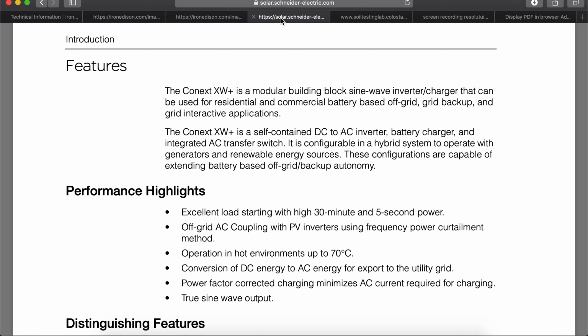The Conext XW Plus is a modular building block sine wave inverter charger that can be used for residential and commercial battery-based, off-grid, grid backup, and grid interactive applications. The Conext XW Plus inverter charger is a self-contained DC to AC inverter, a battery charger, and integrated AC transfer switch. It is configurable in a hybrid system to operate with generators and renewable energy sources. These configurations are capable of extending battery-based off-grid and backup autonomy.